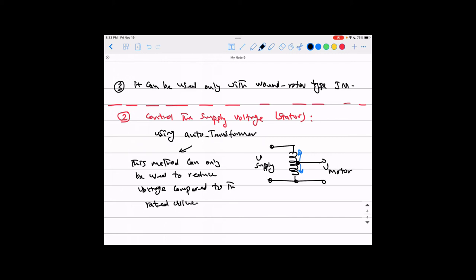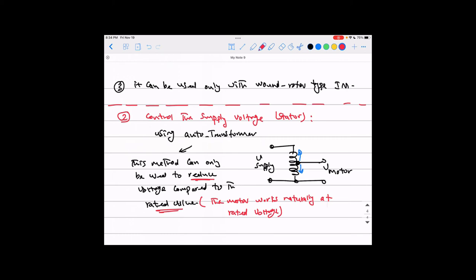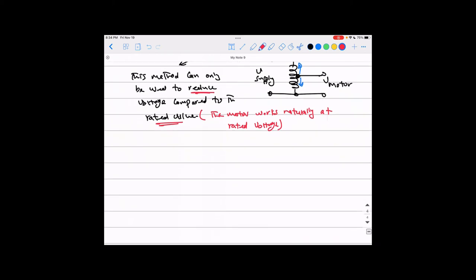Here in North America, for low-voltage applications the grid is 208 V at 60 Hz, and the motor works at this rated value. To increase the voltage above rated would burn the windings — that is forbidden. So you can only reduce the voltage, not increase it. The motor works naturally at rated voltage, so the only option is to reduce it.